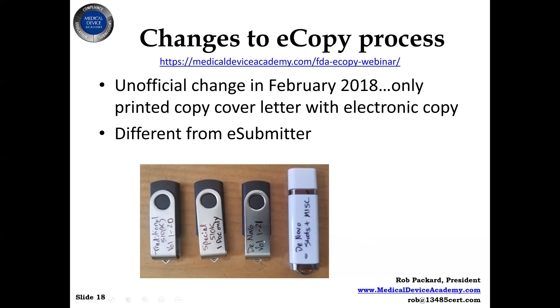This third one here is a de novo submission. Sometimes the submissions are so large that it takes a very long time for the FDA to upload the information to their servers from your USB flash drive. In this particular case, I couldn't even fit all the information on our normal size flash drive and could only fit it on the larger flash drive. So one had volumes 1 through 21, and the other had the statistics and miscellaneous information — split that way because that's how the FDA wanted us to organize it.